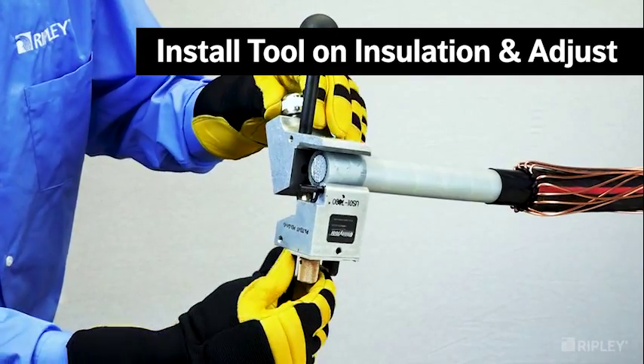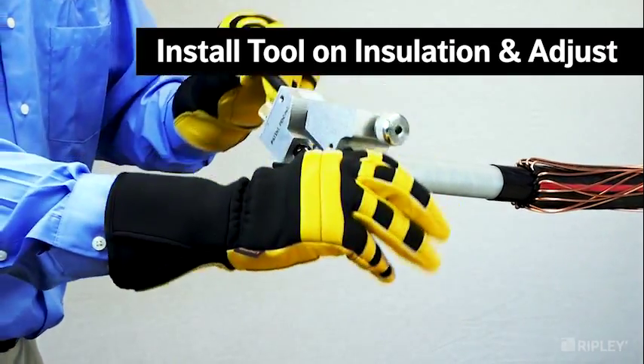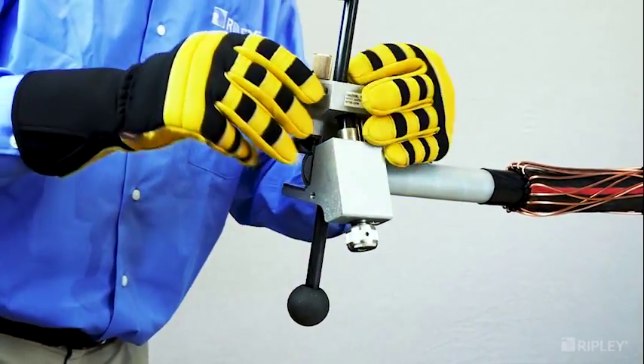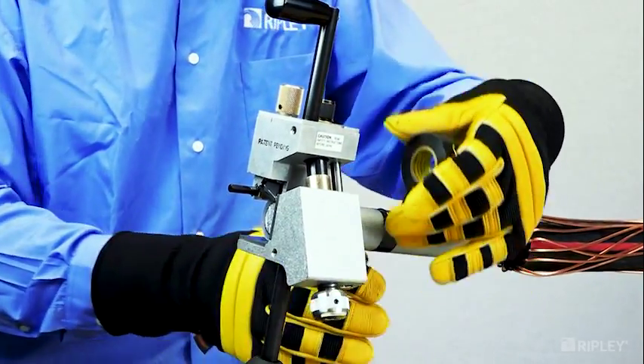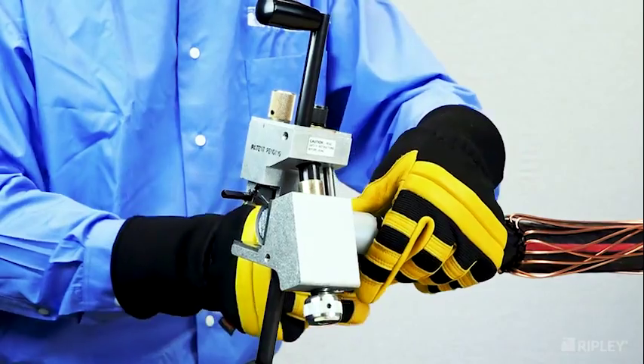Re-install the Infinity around the insulation and re-adjust the blade settings with the blade depth 1-32nd of an inch to 1-16th of an inch above the conductor. Set the blade angle to 10 degrees.